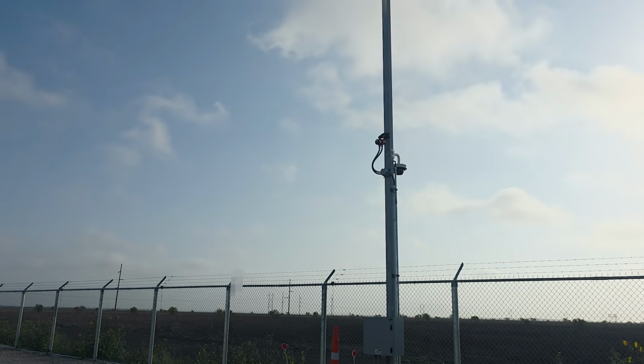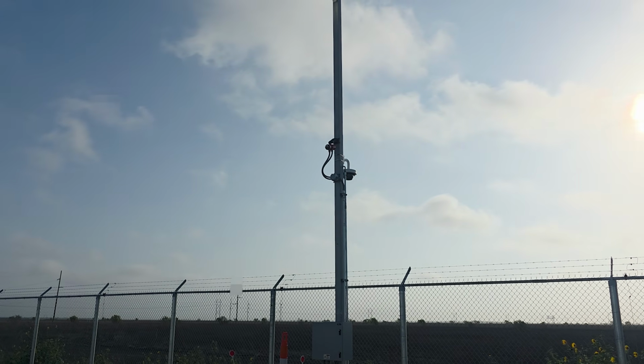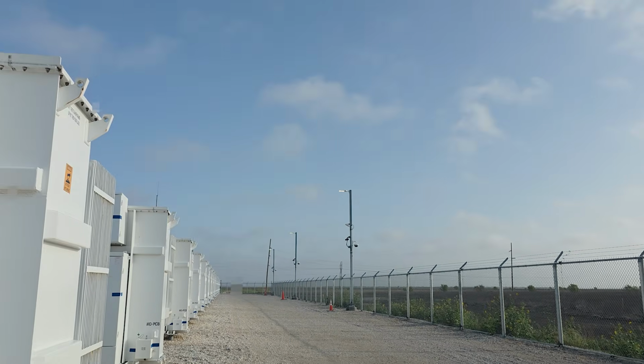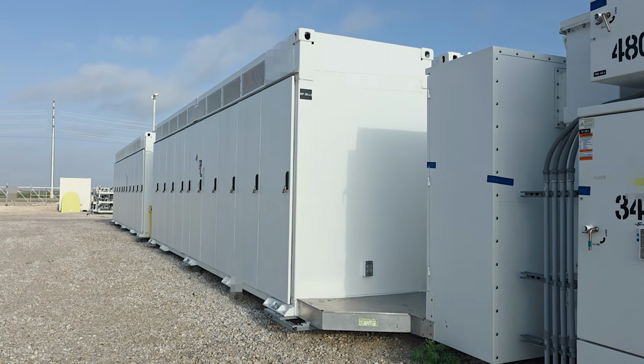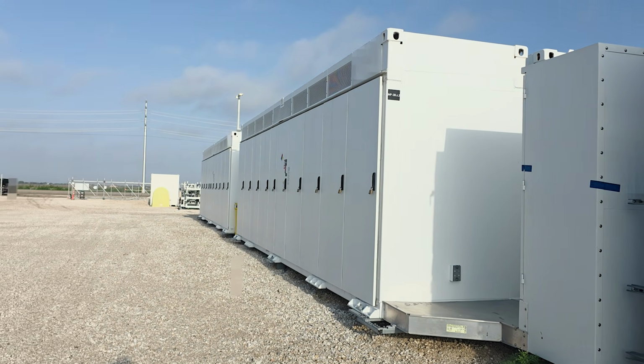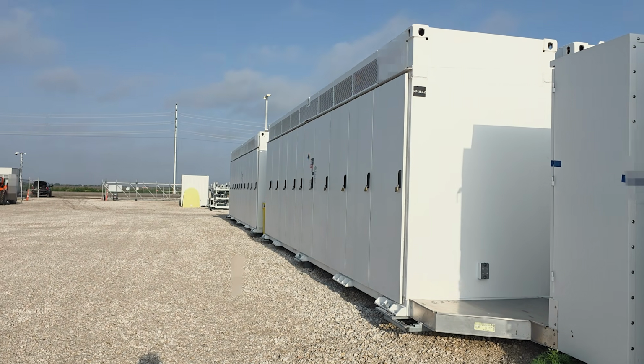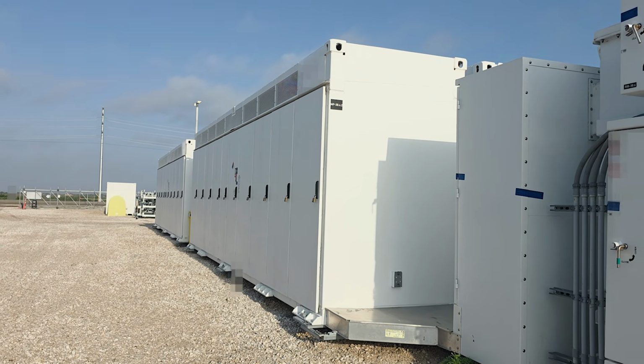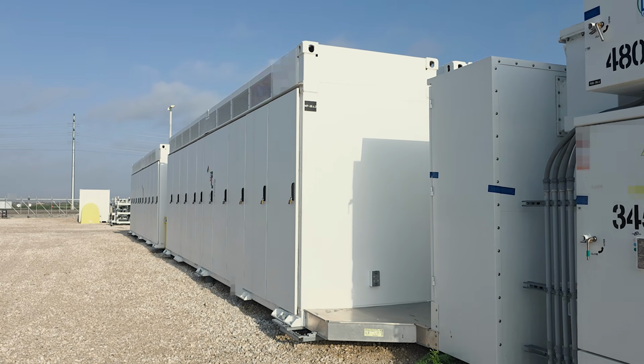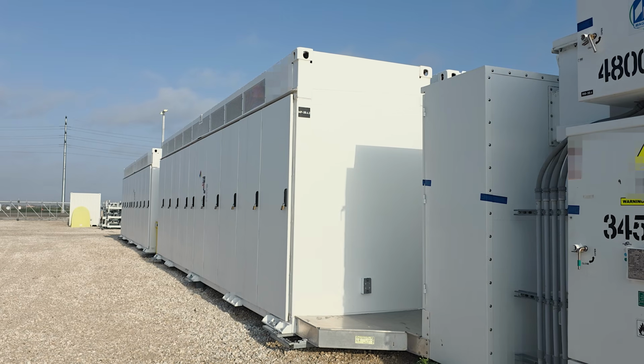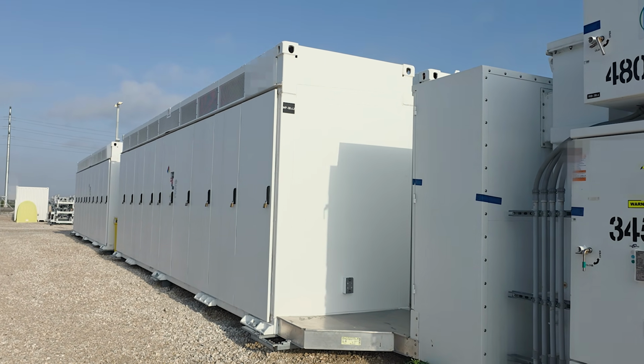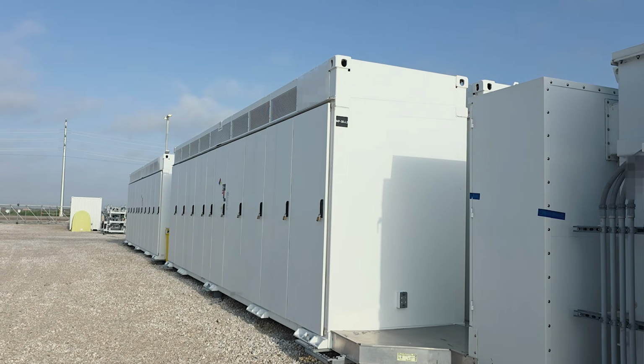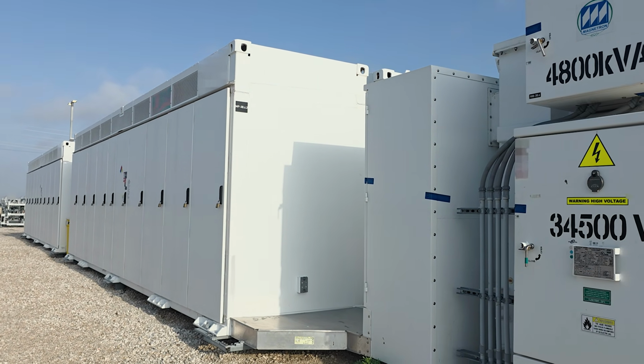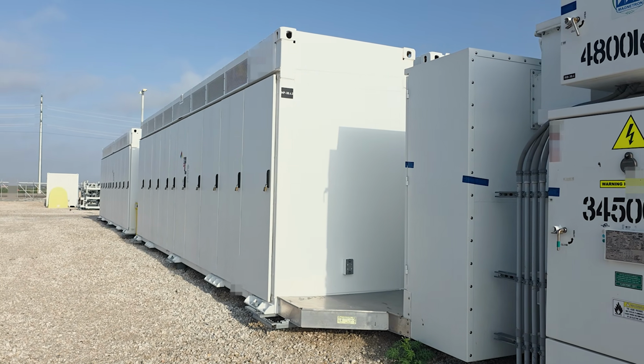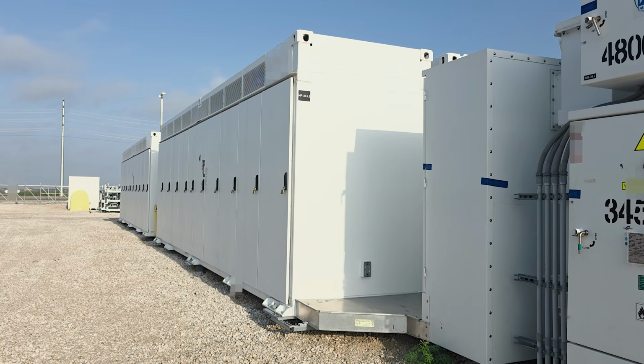There is an optical sensor or thermal sensor on these, and they are programmed to see heat coming from certain batteries. So if that camera sees heat coming from, say, that far battery, it will say, hey, that far battery is burning up and we need to do whatever we need to do. That could be shut off all the batteries, shut off the whole farm. That could be shut off the farm and call the fire department. It's endless. But that system is programmed, and they have to test everything to show a heat source for each individual battery. So if one particular battery is heating up or is on fire, these cameras will read that information and know exactly what battery is on fire.